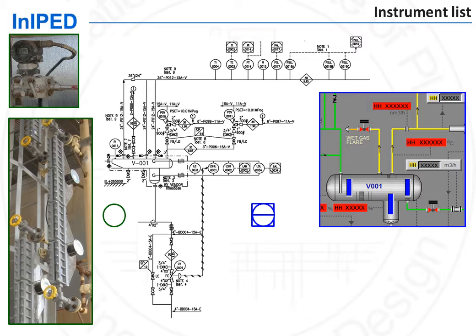There are two types of instruments. Field instruments, which are depicted on the P&ID by means of a circle, such as this pressure indicator. And virtual, also called soft instruments, which are displays on control systems screens or signals inside systems. These instruments are depicted on the P&IDs with a square frame. So this pressure indication is available on the screen of the control system, remotely from the control room, whereas this pressure indication is only available locally.